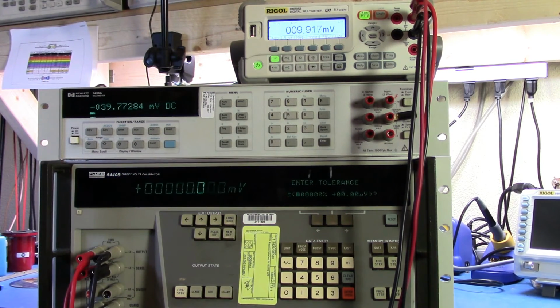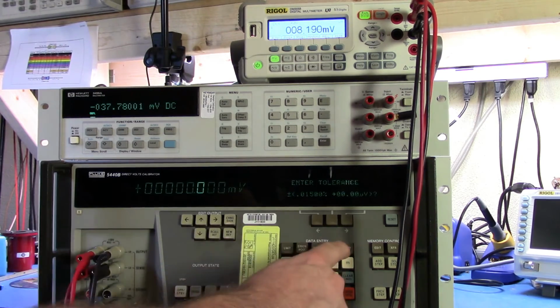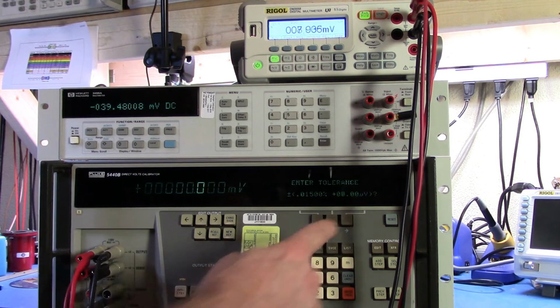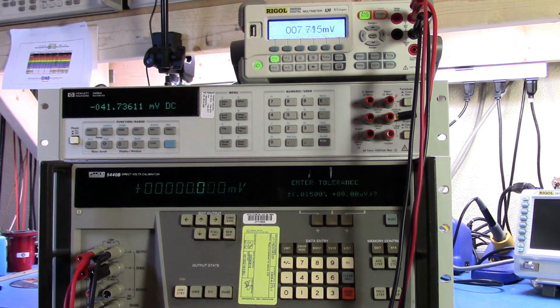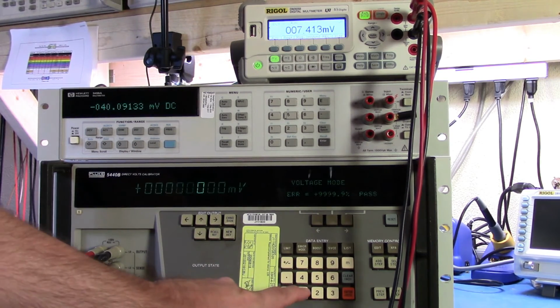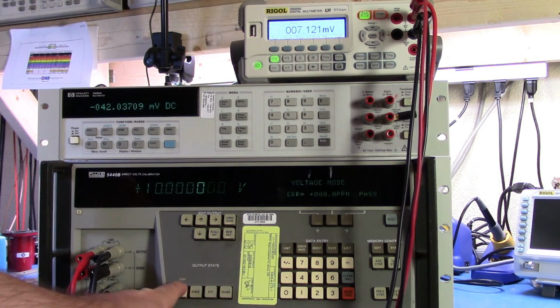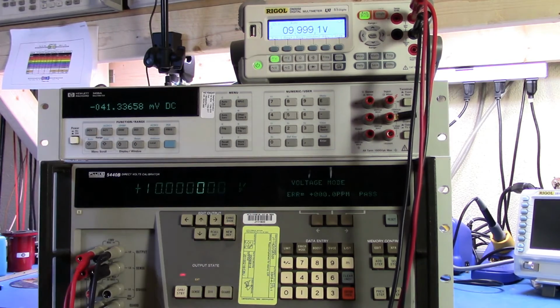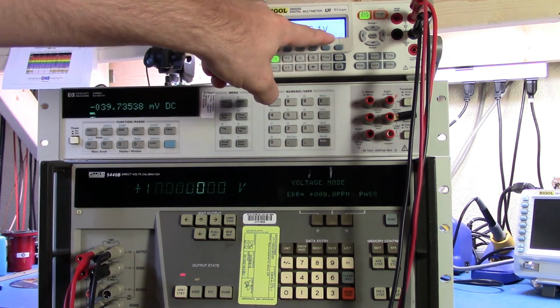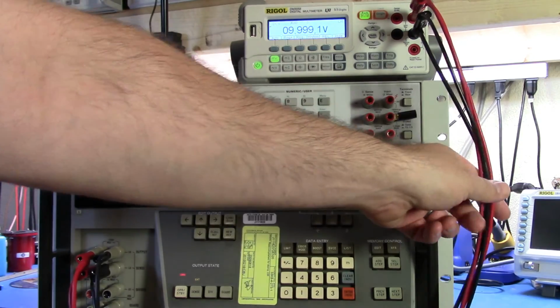Let me go to error mode again and set the error tolerance. It just so happens that if we're looking at 10 volts, I know the error range is 0.015% of the reading, and it's also going to be 800 microvolts according to the specs of the unit. Now if I set 10 volts, press enter and turn it on, and turn on external sensing, we'll see that we get 9.9991, and because I have 10 volts here, we've got 0 ppm error.